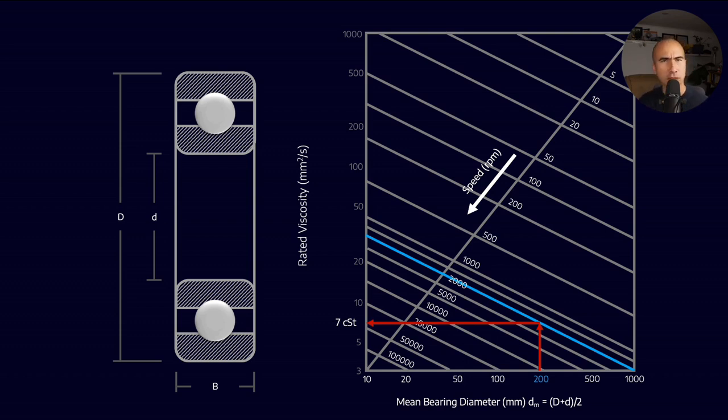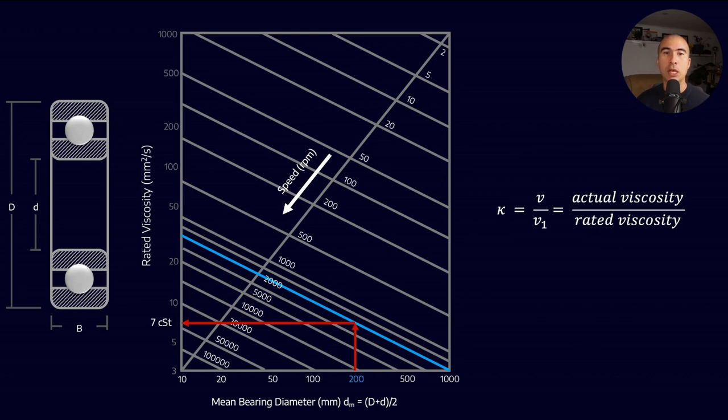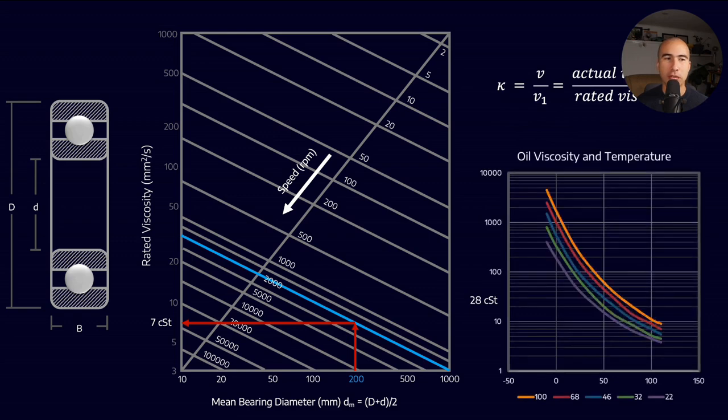Seven centistokes seems really low, but we need to apply the kappa ratio calculation. The kappa ratio defines the ratio between actual viscosity and rated viscosity. We look at actual viscosity in our application. If the bearing operates at 50 degrees Celsius with ISO 46 lubricant, that gives 28 centistokes actual viscosity at operating temperature. We take 28 divided by seven, giving a kappa ratio of four.